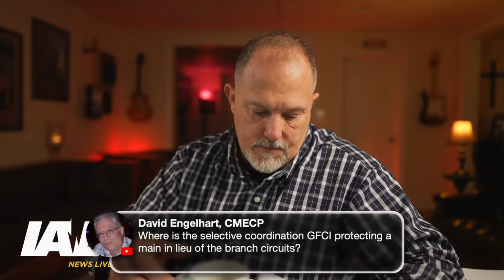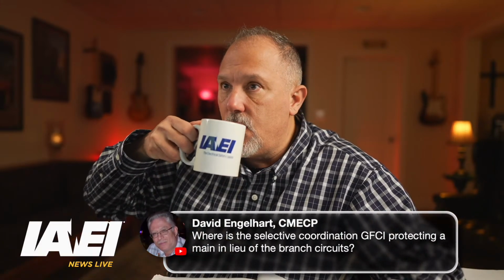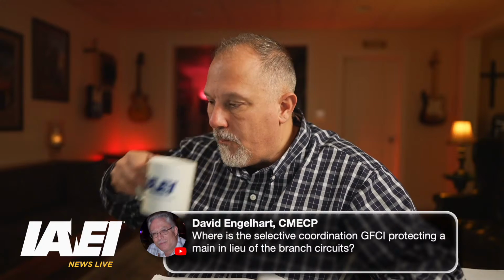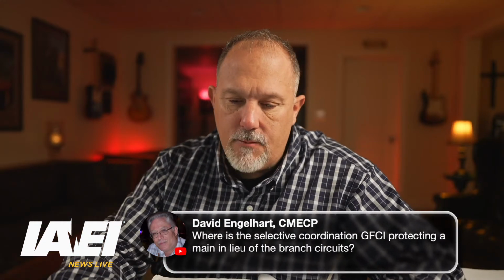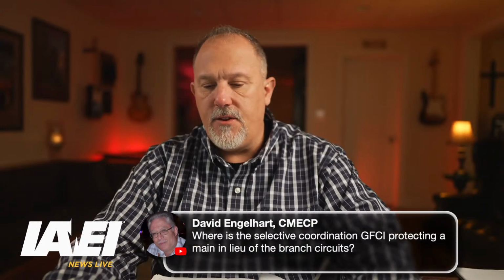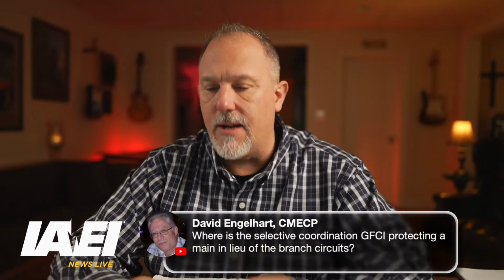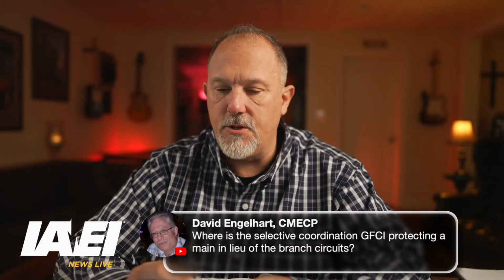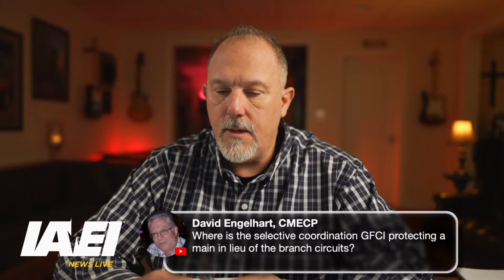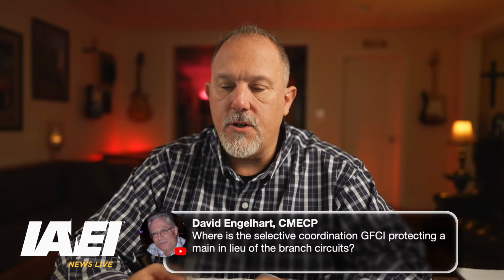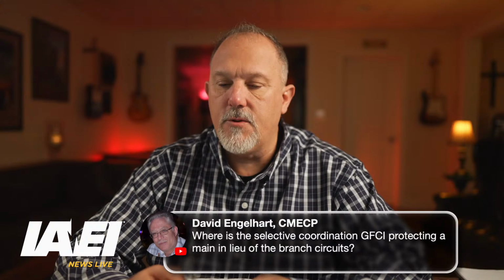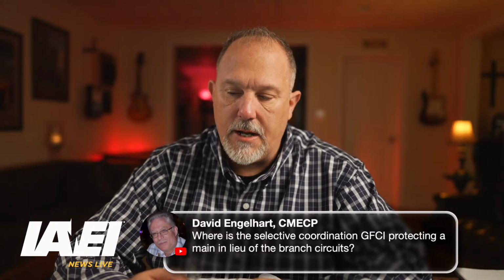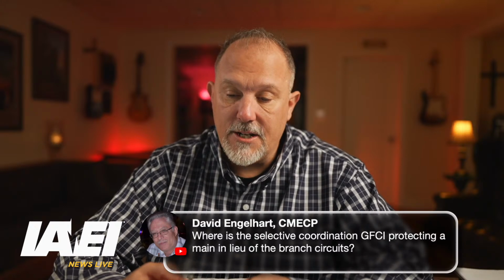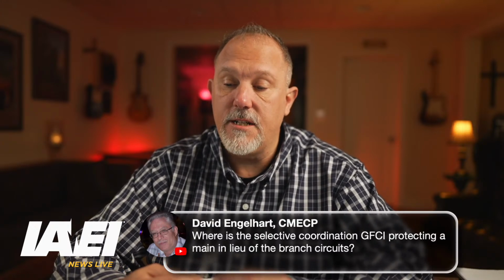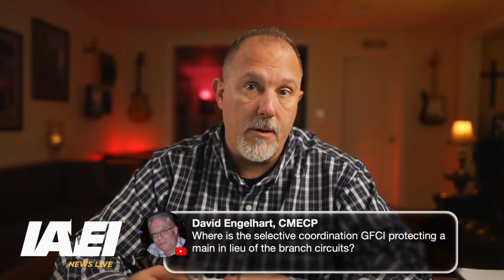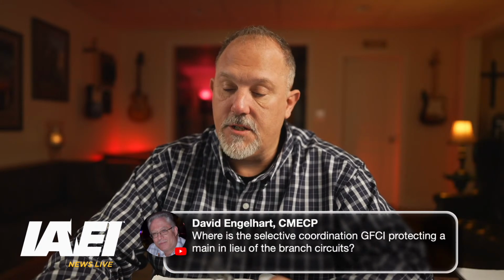All right, so let's keep going. It's 215.12, so I was not at 12. We jumped ahead. So we did 215.10, that's your GFPE, and 215.11, circuits derived from autotransformers. Feeders shall not be derived from autotransformers unless the system supplied has a grounded conductor that is electrically connected to a grounded conductor of the system supplying the autotransformer. And there are two exceptions to that.